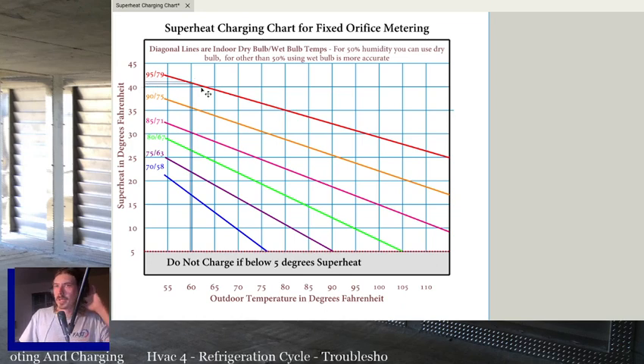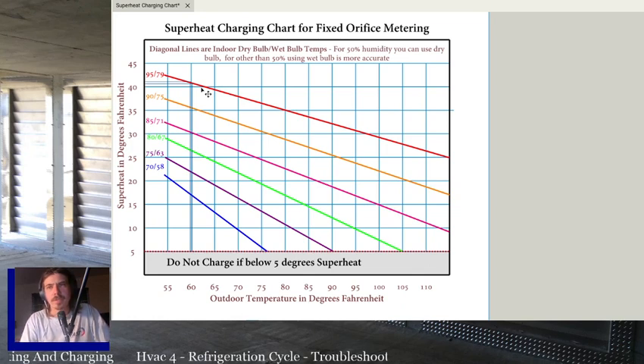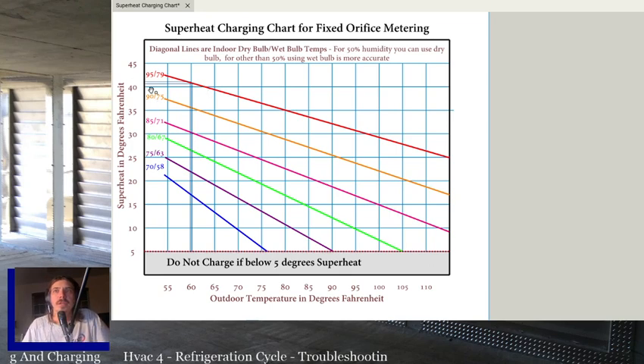So if your indoor temperature is high and your outdoor temperature is low, that is when you're going to have the biggest superheat numbers. So just remember that if you're working on a system with that combination, a low outdoor temp with a high indoor temp, that's when your superheat's going to be high. Basically, anytime your indoor temperature is high, your superheat's going to be high, because you're going to be picking up a lot of heat.